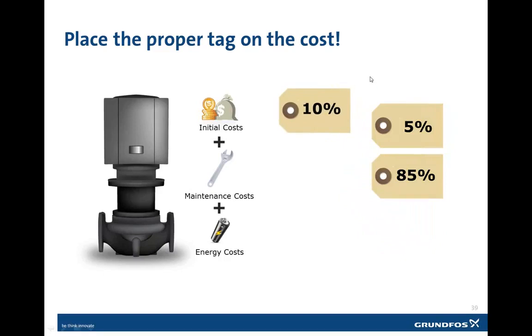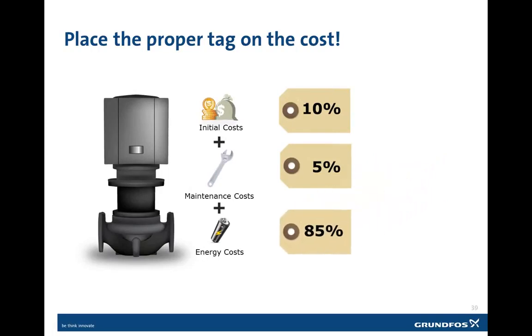Actually, when we're talking about a variable speed type of system, where we're adding the controls and the variable speed drive, the initial costs equate to about 10% of the cost for the system. And then the maintenance costs are reduced to about 5% because of the variable speed drive and the proper control methods, especially if we're using a Magna 3 pump. And really, the energy costs are the largest portion. So they're not all three equal. When we look at the initial costs, if we guess 10%, that's reasonable if we're using a Magna 3 installation because it includes the pump, the motor, variable speed drive, the sensing elements, as well as the controller.